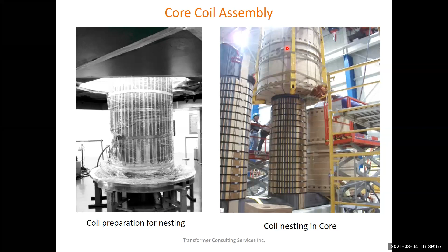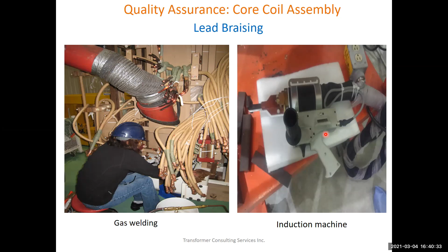So now on the left-hand side, you can see that person is doing the lead work using the old gas welding machine. When that person uses the gas welding machine, it creates flame. Not only flame, it can also create metal particles. If it creates those metal particles, it can cause the failure of the transformer in the long run. Whereas in the modern factory, they use an induction machine. When you are using the induction machine for the lead work, you are not creating any fumes or any particles. That means you are not compromising the quality of the transformer.